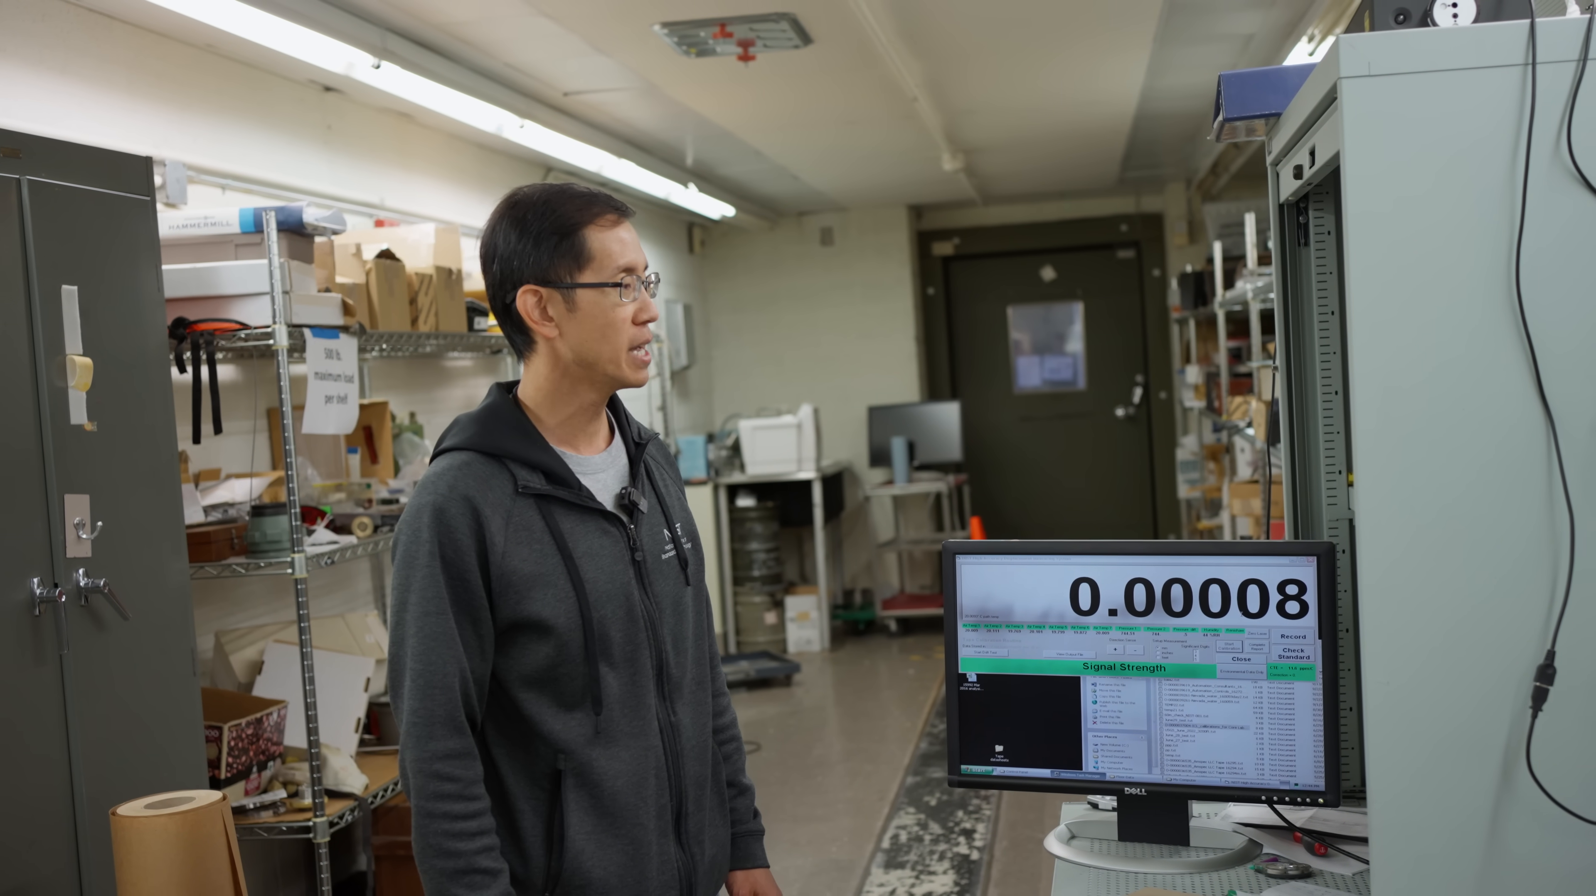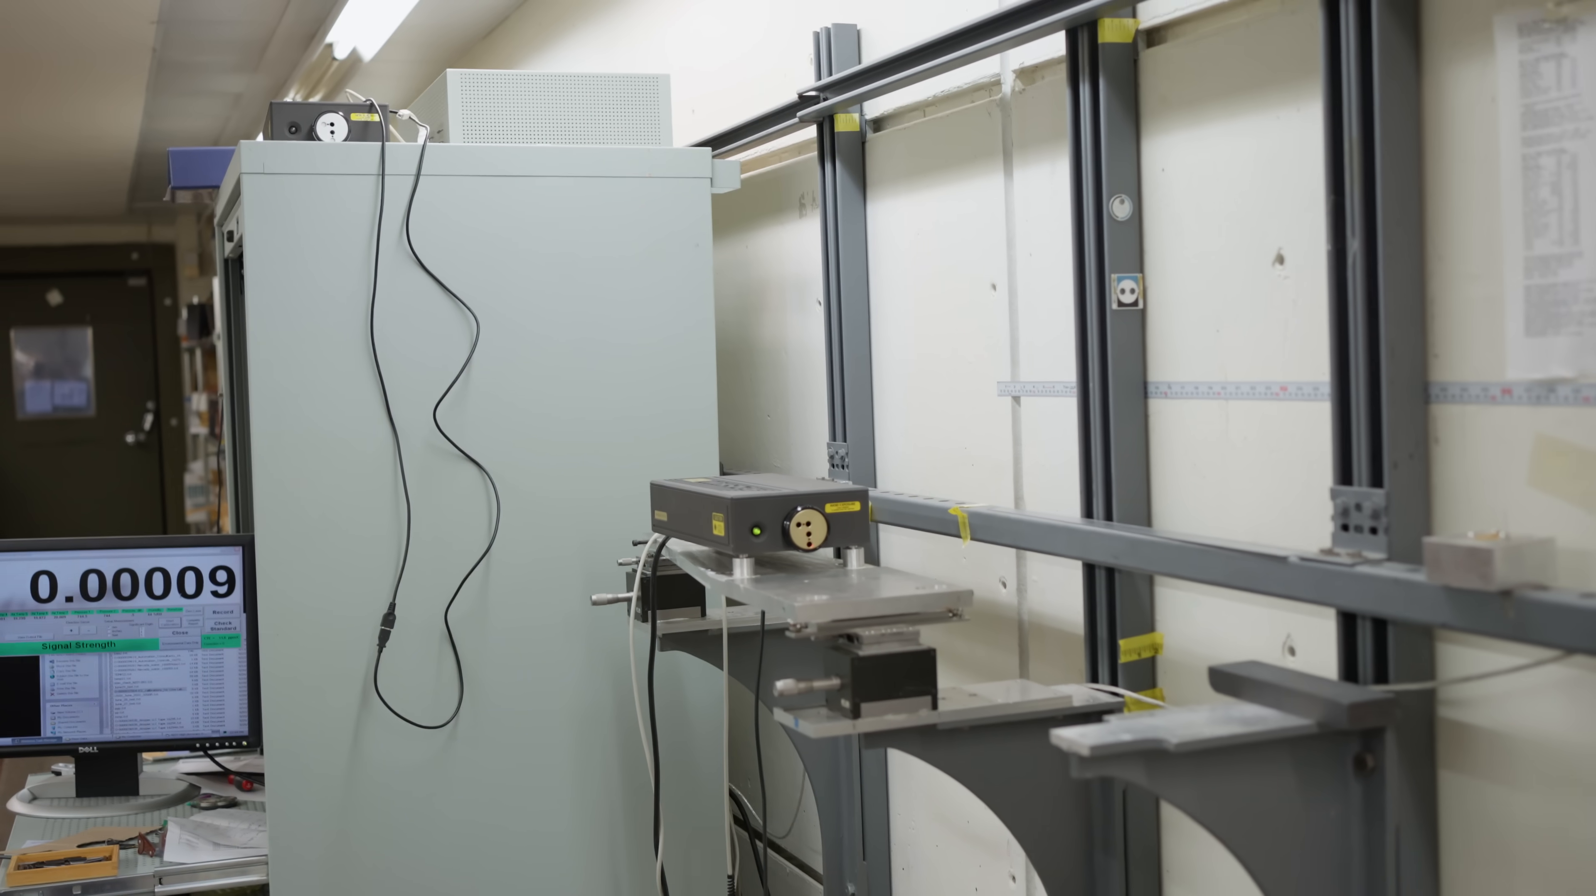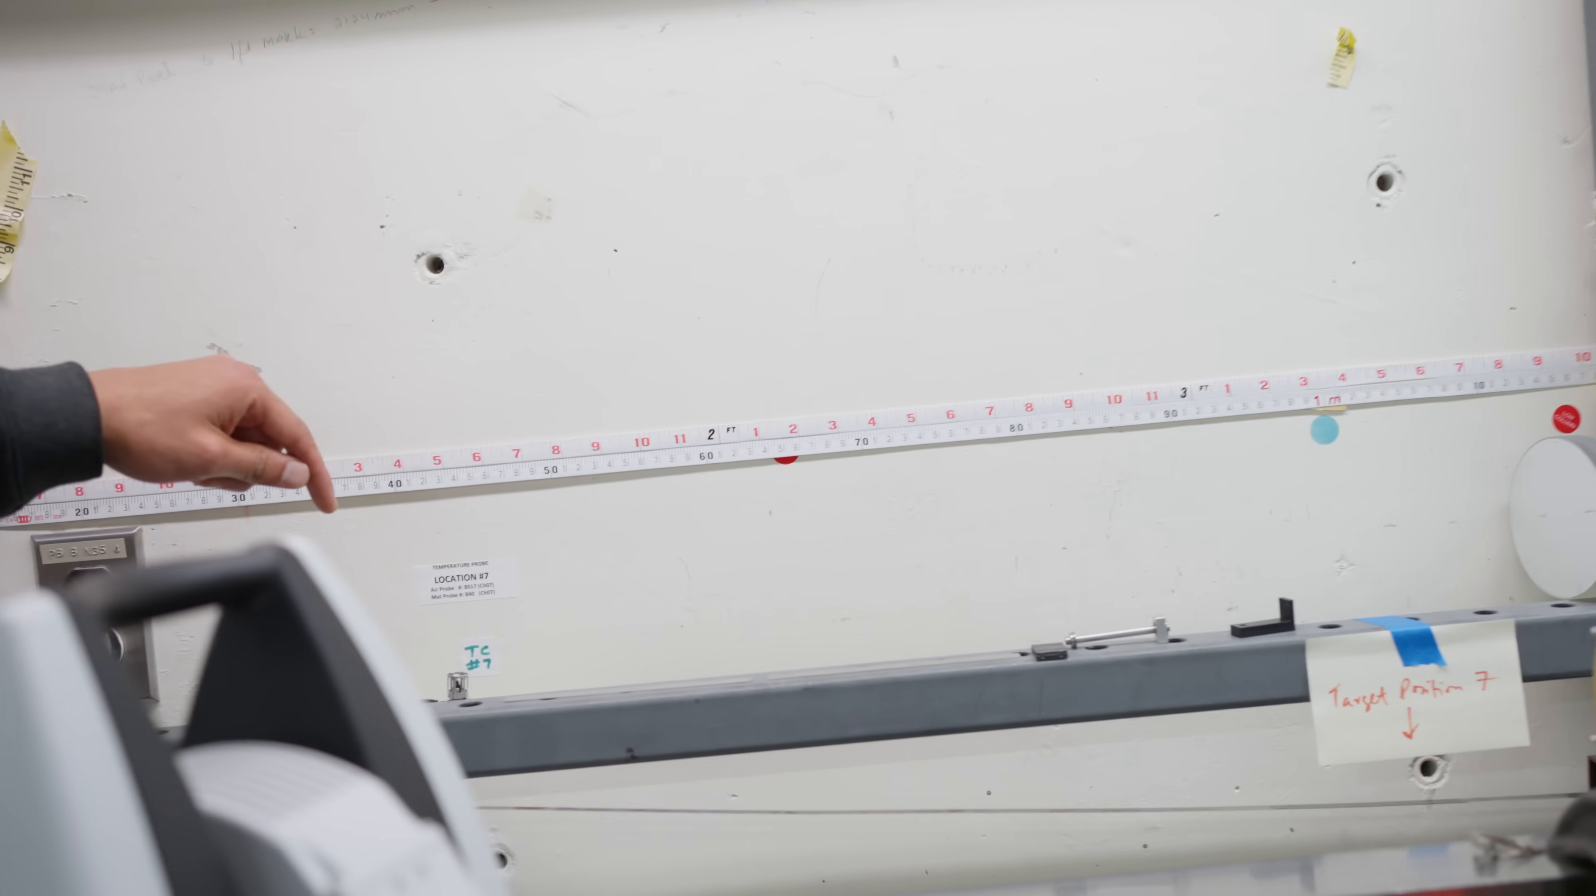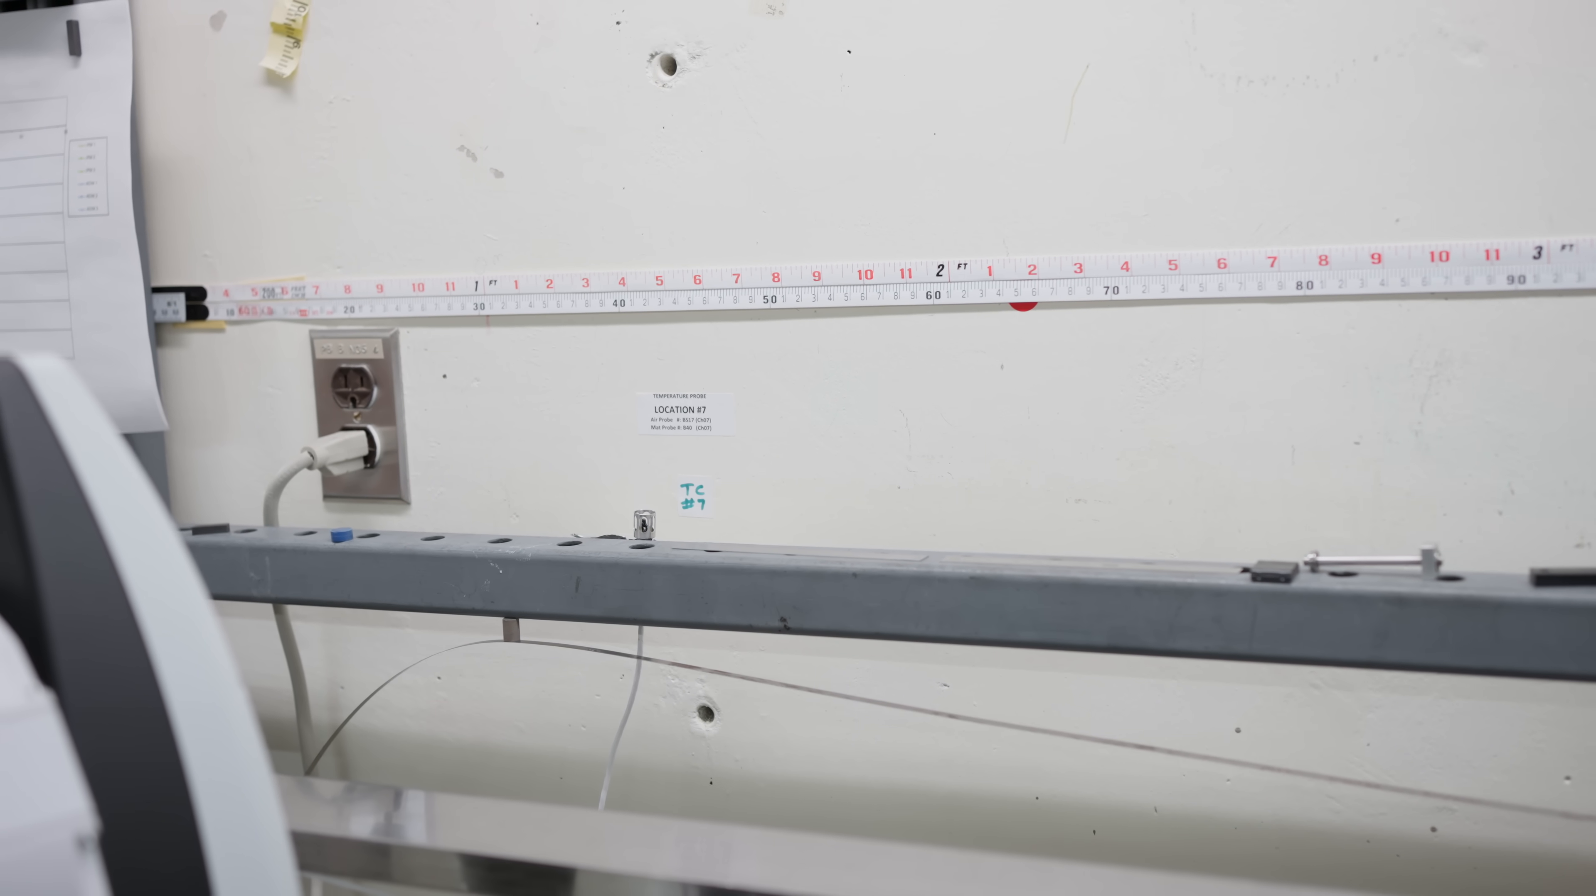And as far as data goes, we have data from our laser interferometer and 14 temperature sensors along the measuring bench. You can't really see them very well. There's one right here which measures air temperature, and then a few more pasted under the bench, under thick, insulating foam, to measure the tape bench temperature.